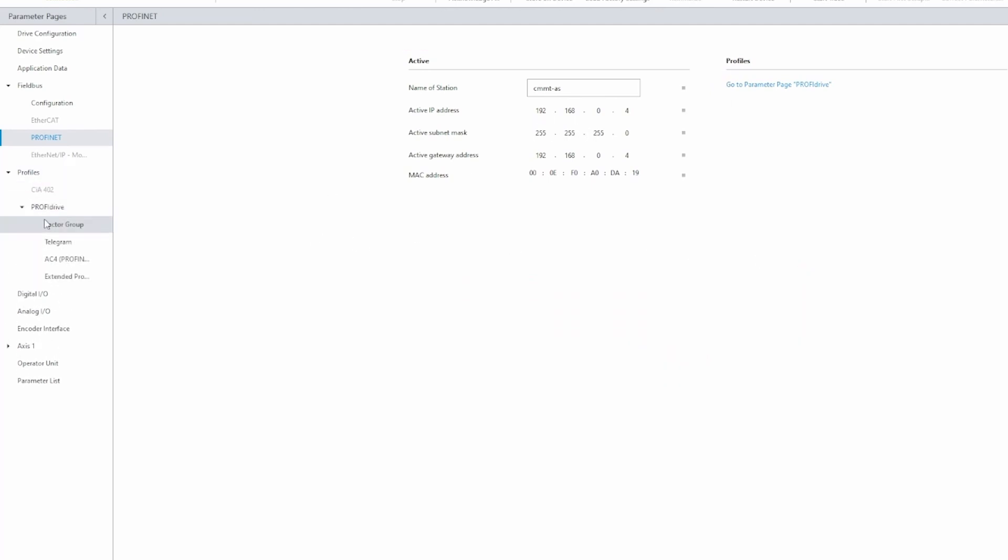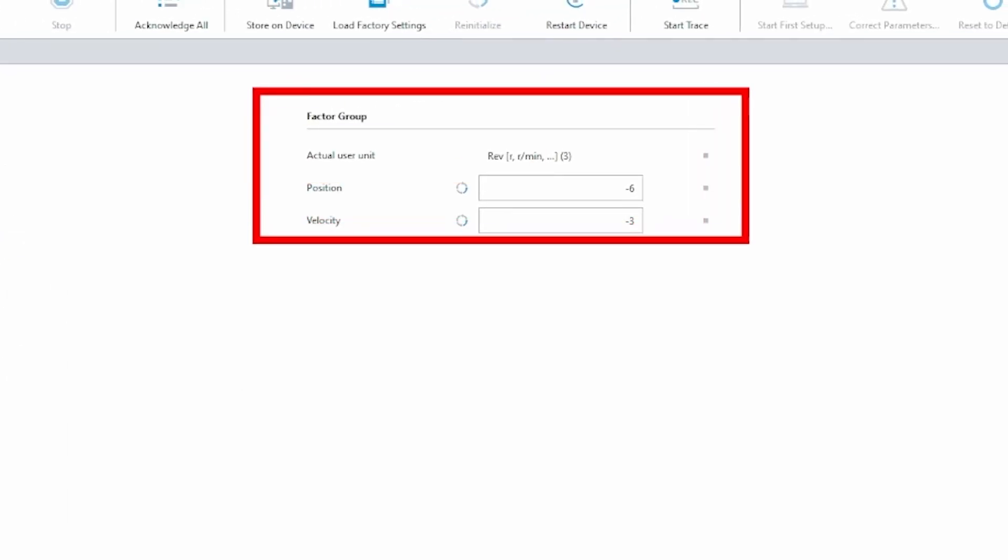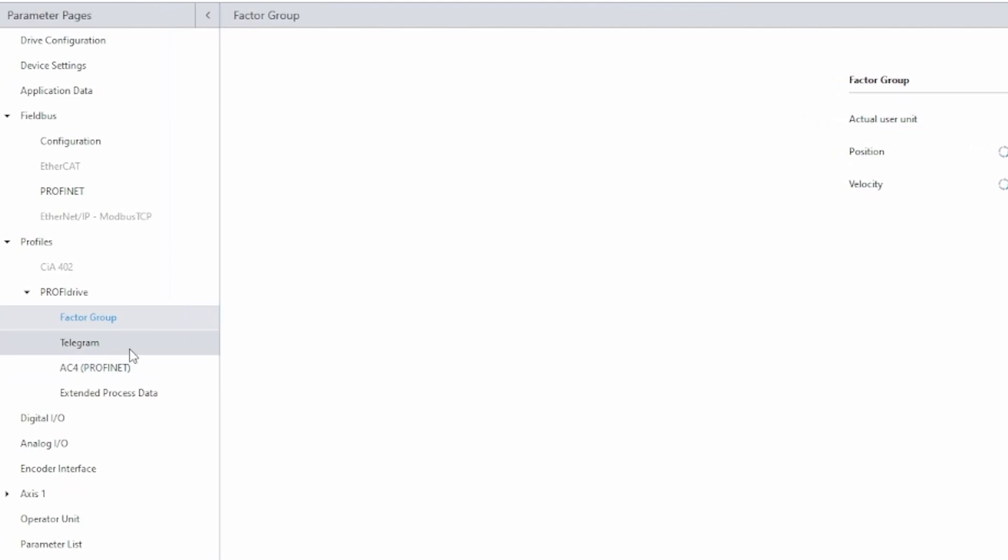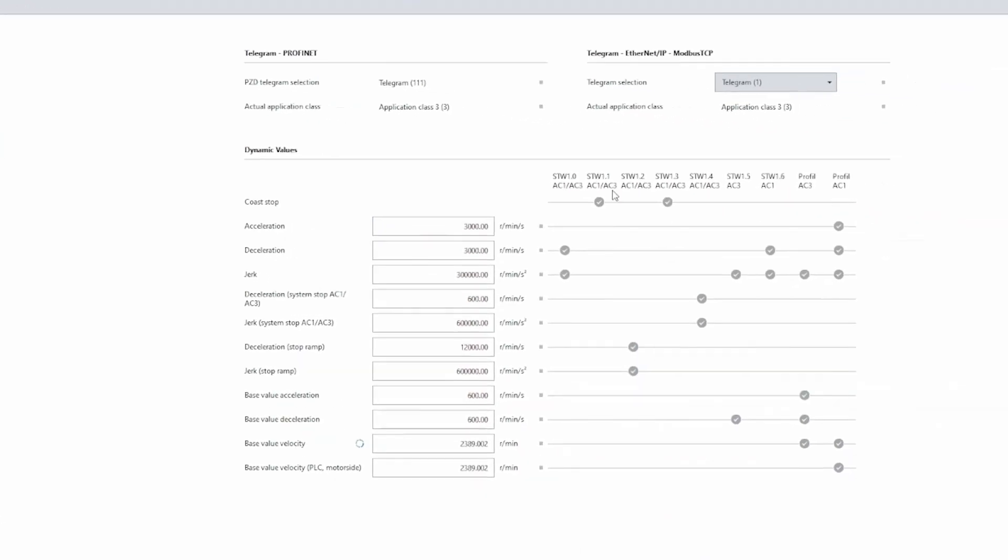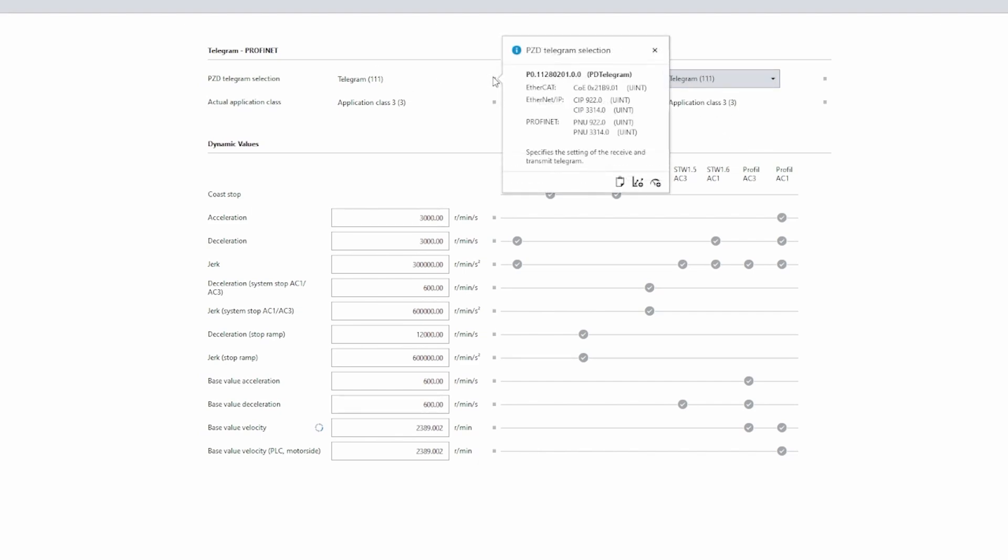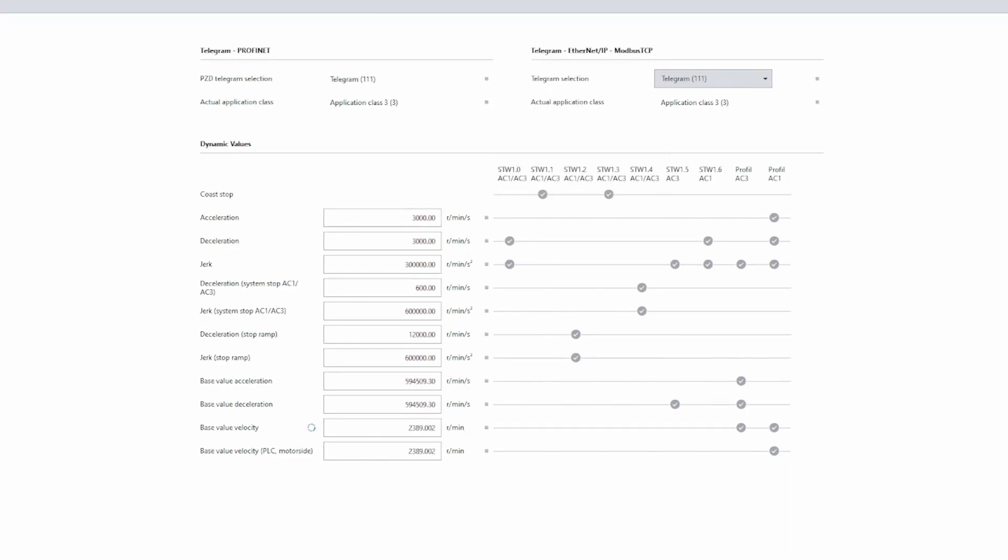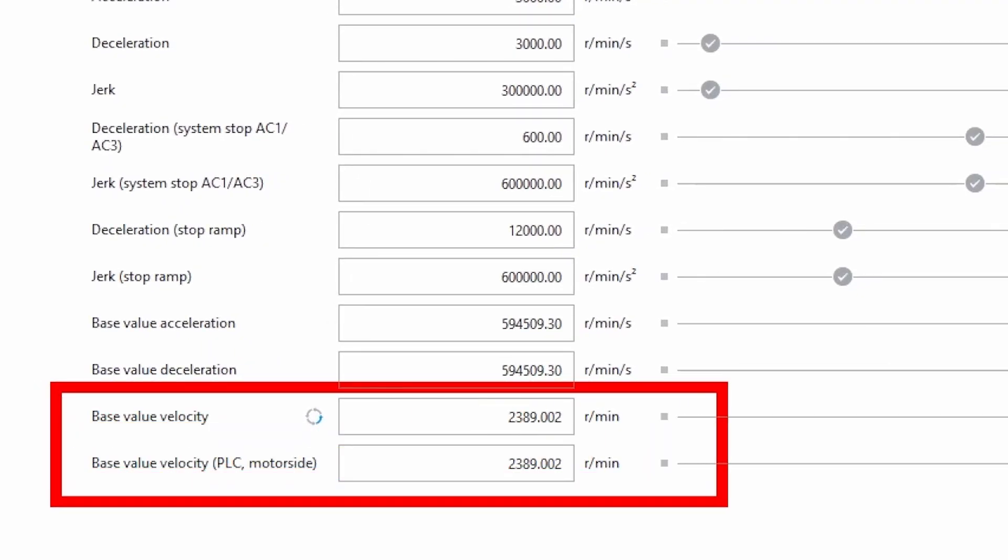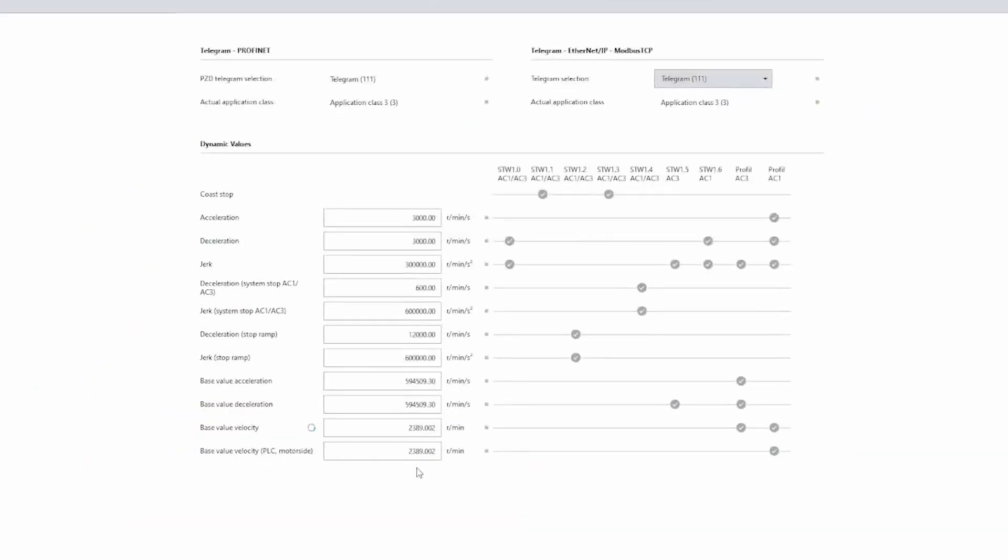So now you're going to drop down profiles, ProfiDrive, and I want to show you factor group. So position is set to negative six and velocity is set to negative three. This sets your units for TIA Portal by moving the decimal six places and three places so that you get more resolution on your position and velocity. Now we're going to go to telegram and we will set it to telegram 111. This feeds the proper array of data to the PLC so that we can do the point-to-point function block. The next thing to take note of on the screen is the base value velocity down here. We are going to take this value and copy and paste it into TIA Portal later for the point of scaling the velocity correctly.